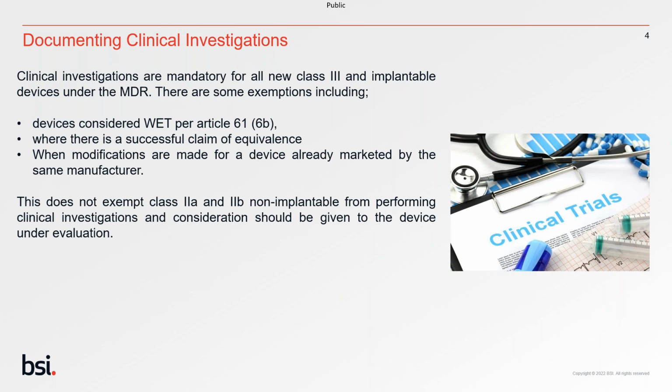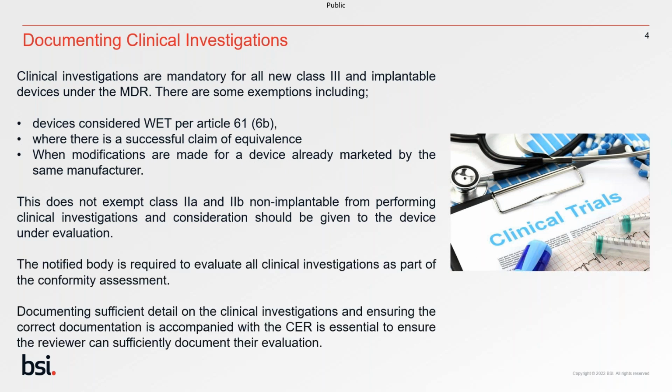So it is worth saying though, just because class 3 and implantable devices are told that they should perform clinical investigations for the MDR, sometimes we do see that interpreted as class 2A and 2B non-implantable devices not requiring clinical investigations, and that actually is incorrect. Really, consideration should be given to the device under evaluation, the performance and claims made for the device, to determine whether or not a clinical investigation is appropriate. So really, consideration still needs to be given to class 2A and 2B non-implantable devices.